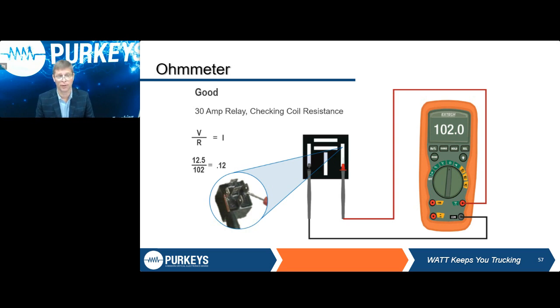So the first thing we're going to check with this relay, we're going to grab our meter, put it on ohms, and go across the coil. On this one right now, it says we have a resistance of 102 ohms. Very important. Is that good or bad? If you don't know what the specs are, you can't even answer that question.